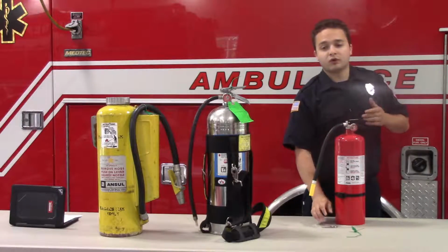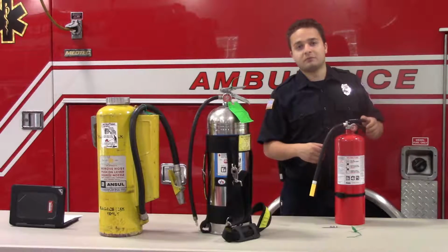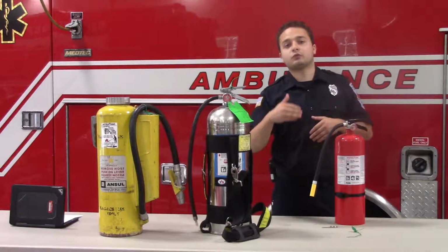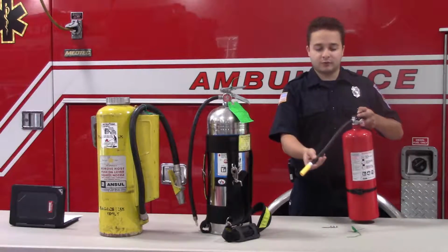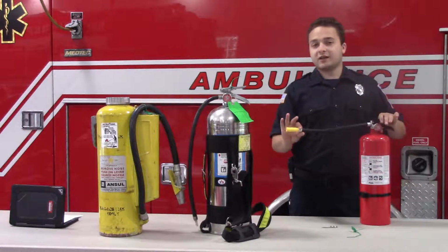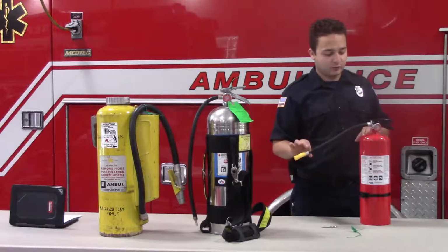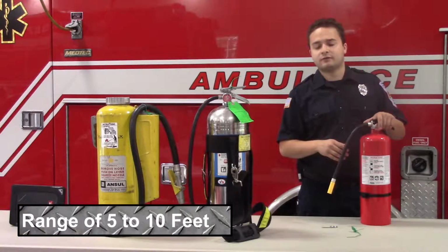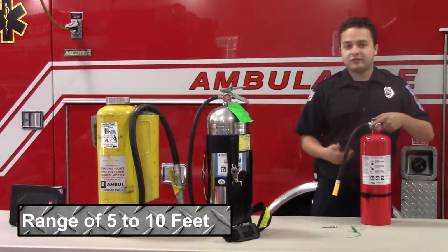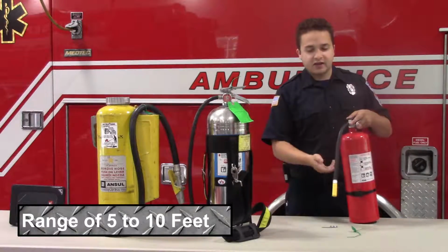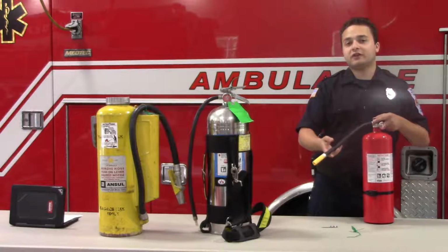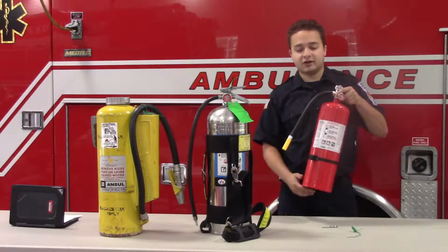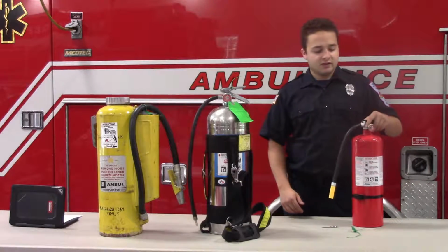What's important to know when you're walking up to the fire with an extinguisher is not to get too close. The minute you start to feel heat, that's when you can stop and begin the extinguishment. Dry chemical, depending on the size of the extinguisher, will put out product about 5 to 10 feet. So if you're back 5 to 10 feet, it will still reach. We sweep at the base of the fire until either A, the fire goes out, or it becomes too much, or we have run out of product in the extinguisher.